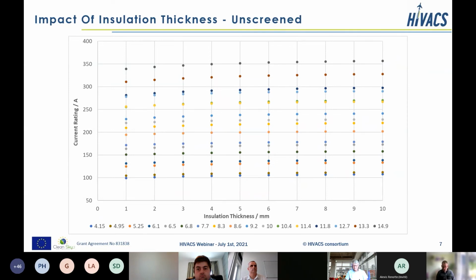For me in the modeling work, the most surprising result on a personal level was the lack of dependence of insulation thickness on the rating of a cable. So this was actually a model for unscreened cable, but you could equally apply it to a screened cable with a sheath connected at one end. And what you can see here, we have a number of cable sizes, which are the values on the legend, ranging from 4mm to 14.9mm conductor diameter. And as a function of insulation thickness, you can see increasing from 1mm insulation to maybe 10mm insulation doesn't significantly impact the current flow that can be passed through the cable.